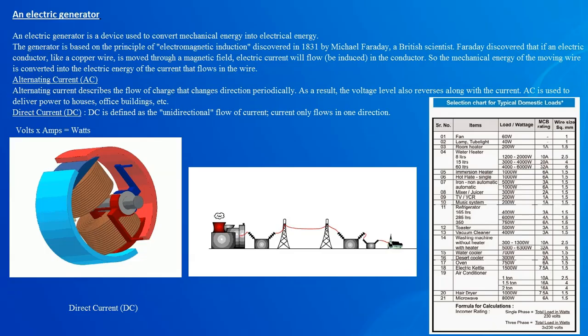Formula: volts multiplied by amps equals watts. Single phase equals total load in watts divided by 230 volts. Three phase equals total load in watts divided by 3 times 230 volts. This is the chart showing typical domestic loads. 1. Fan, 60 watt, 1 square millimeter size wire. 2. Lamp, tube light, 40 watt, 1 square millimeter size wire.